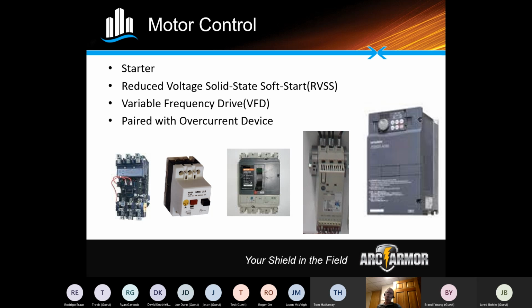The biggest issue we have to worry about with drives is the amount of heat that they generate. They generate a tremendous amount of heat. And when they do generate heat, we have to dissipate it. So you'll either see forced air ventilation on panels, or you'll see air conditioners being provided. So there's a little bit of extra cost above and beyond what a typical panel would require for across the line or full voltage non-reversing, but there's also a lot of added benefits to providing a VFD as the controller. So, any questions on motor control?